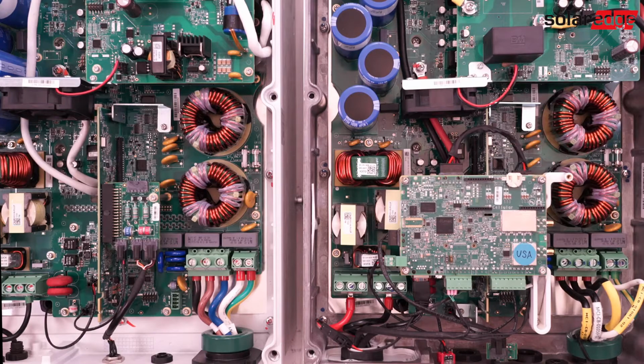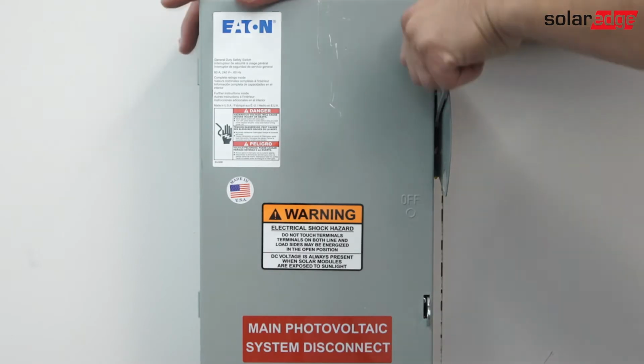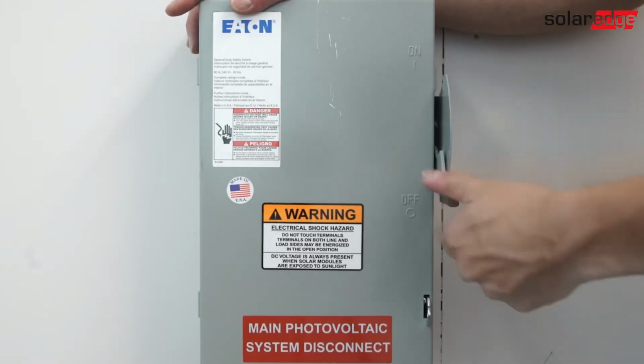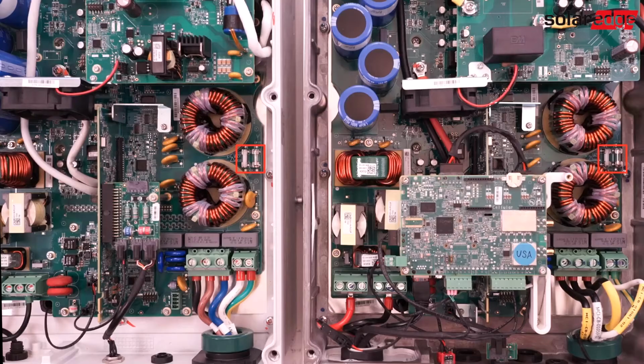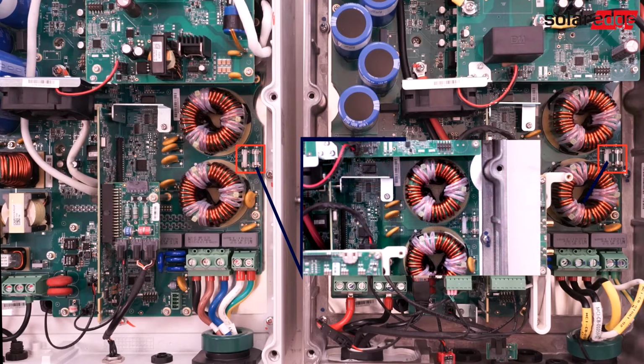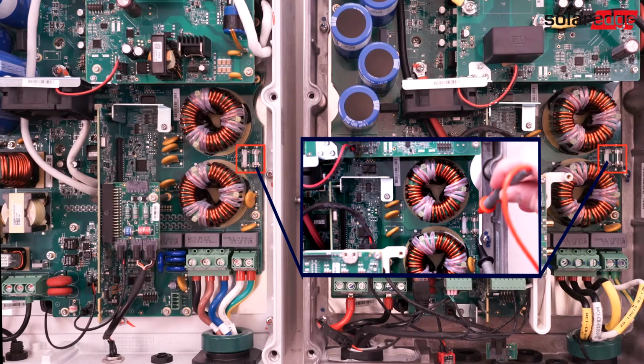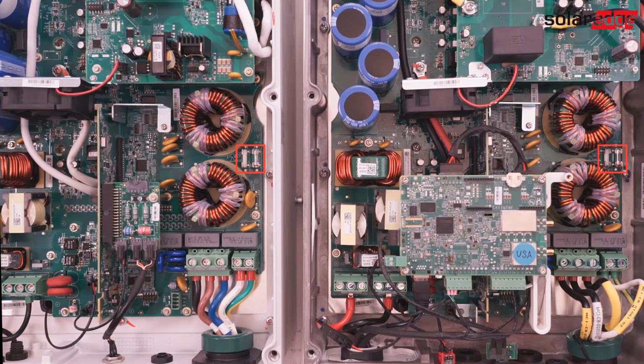Next, remove the covers for both primary and secondary units, and repeat AC voltage tests on the AC connections located in the lower right-hand corner. Next, turn off AC power in order to test for fuse continuity. Using a multimeter, test for continuity on the fuses in the primary and secondary units. If no continuity is found, replace the fuse with a 750 milliamp 250 volt slow blow fuse and attempt to power up the system. If fuses are good, perform the next step in the video.